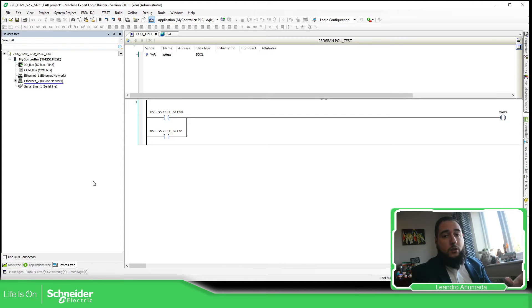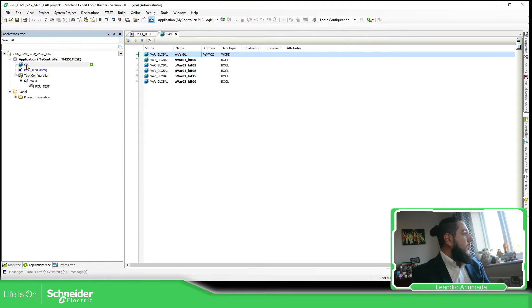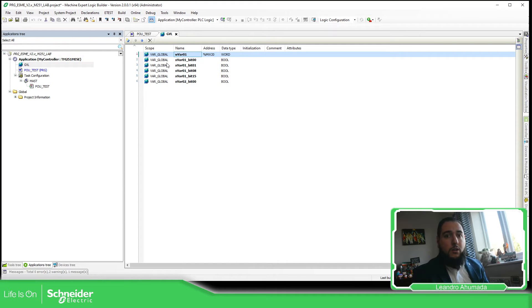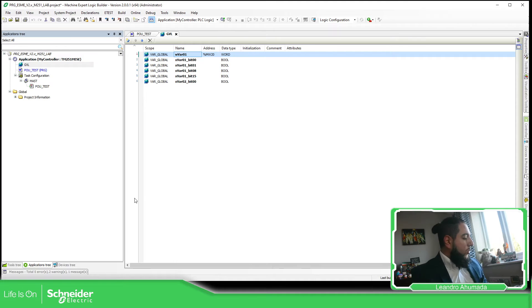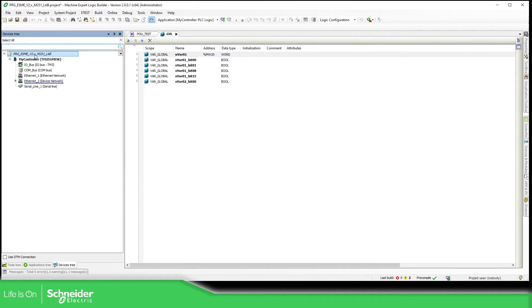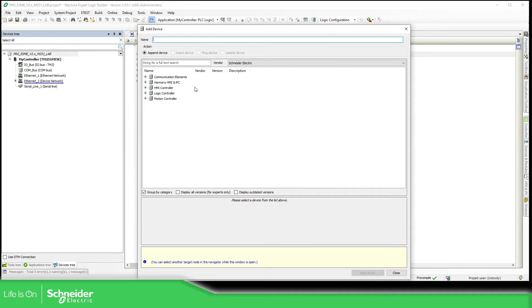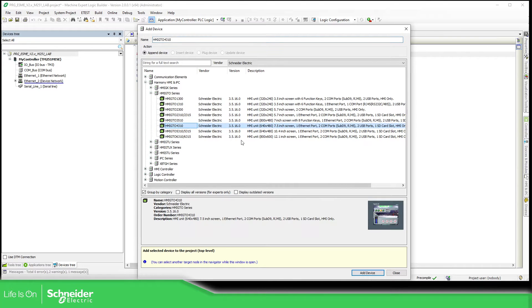I have this small application of the M251, which has a POU in the task and a GVL. The idea is to communicate the HMI to PLC over Ethernet, or it could be over serial. In our case, I'm going to simulate the HMI to be much easier for us. The first thing we need to do is add the HMI in our project. Go to device, right click, add device. In the list, go to the Harmony HMI and IPC. Here you have the list of HMIs or IPCs. I'm going to use the HMI GTO. We just need to wait for this to finish and load the Vijeo Designer part.